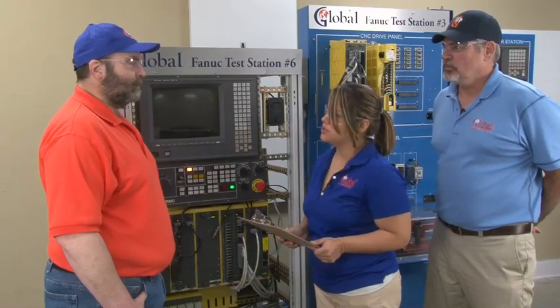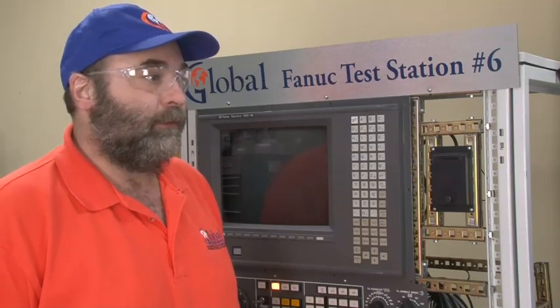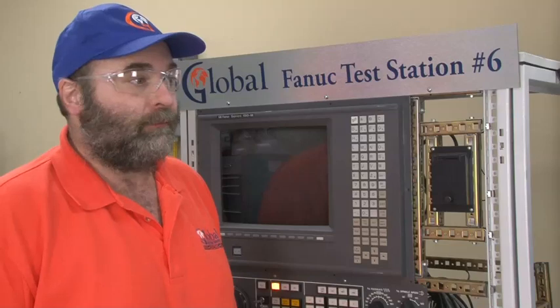Irwin, I have a customer whose display isn't working but his controls are still powering up — how could he troubleshoot this? If the machine is still operating normally, they most likely have a problem with their CRT or the CRT power supply. In either case, they will need to send the unit in for repair.